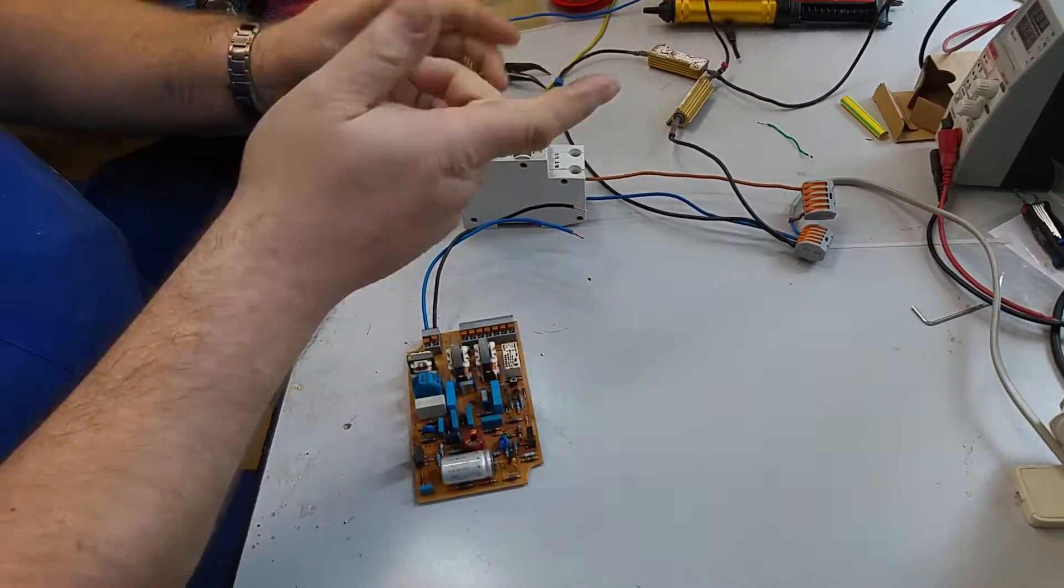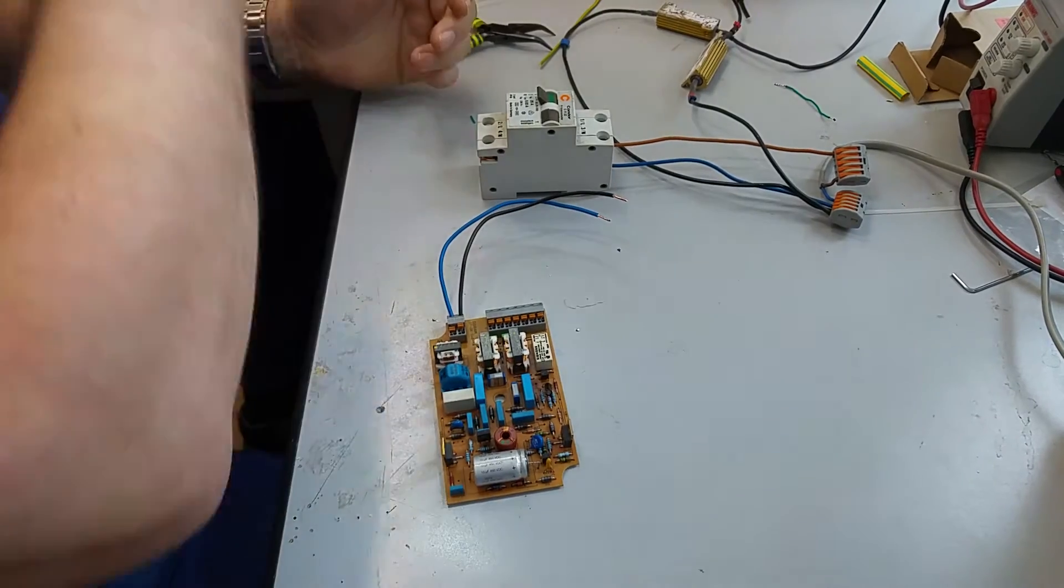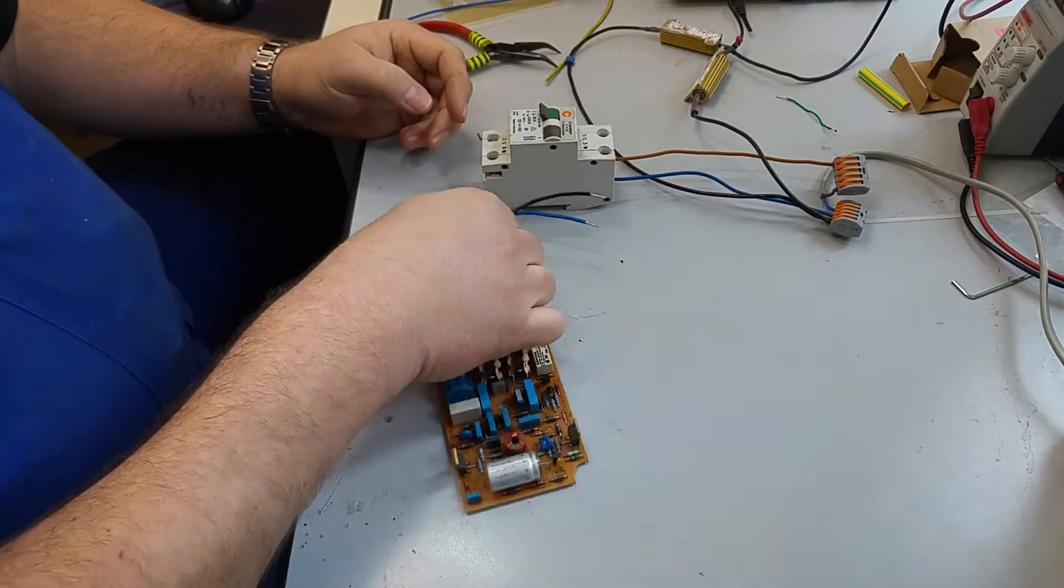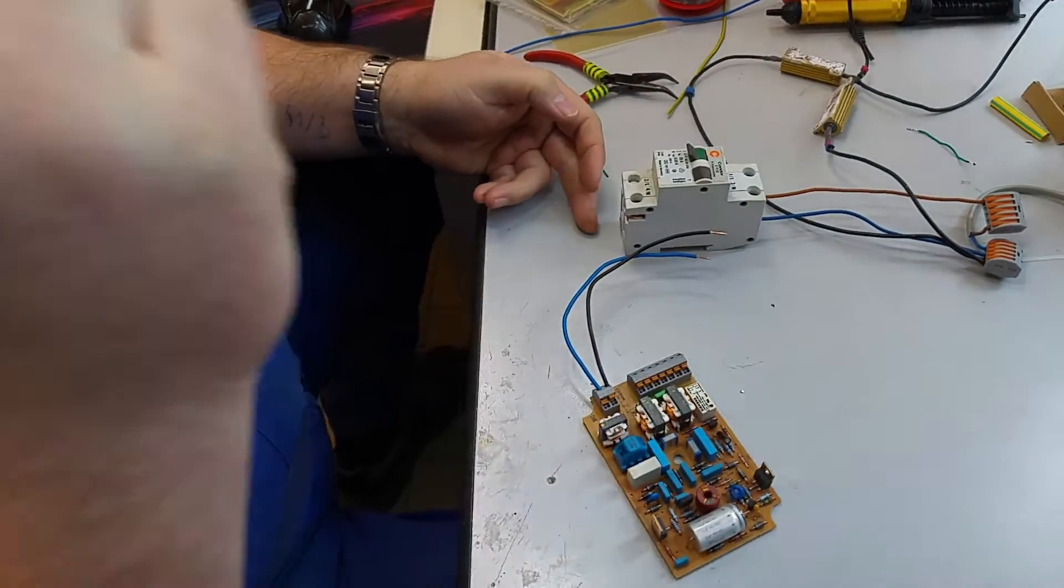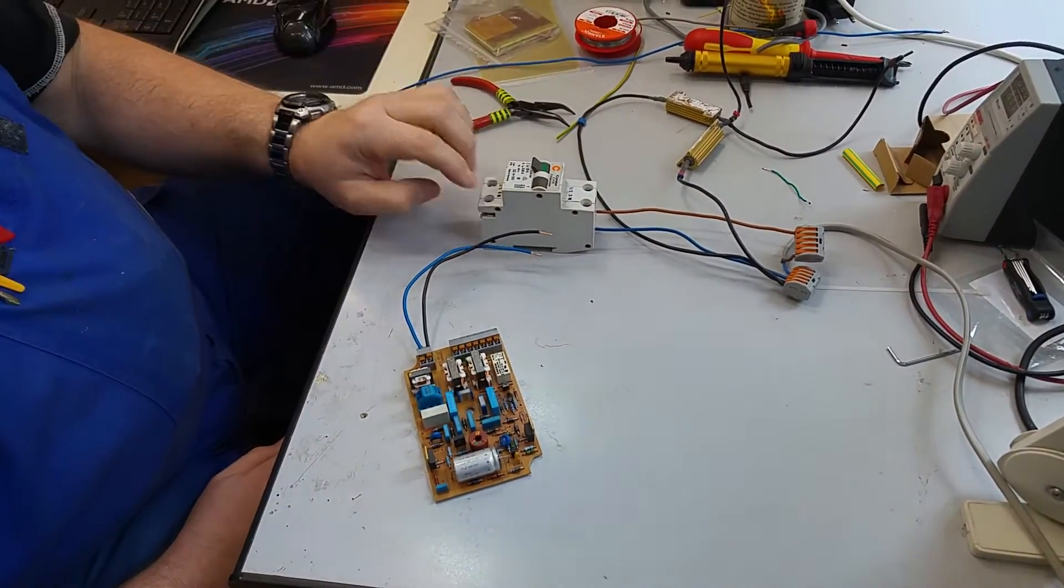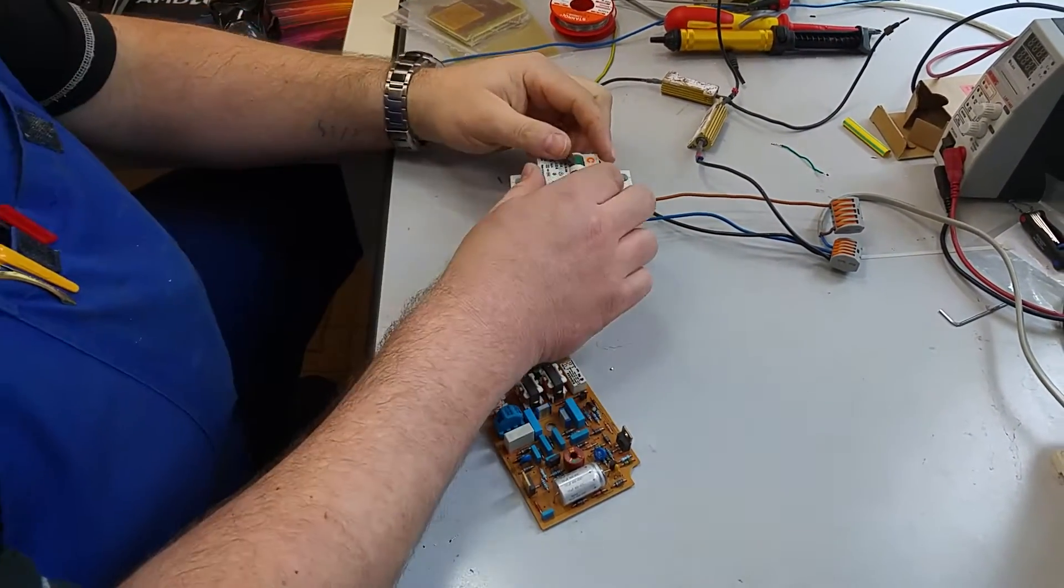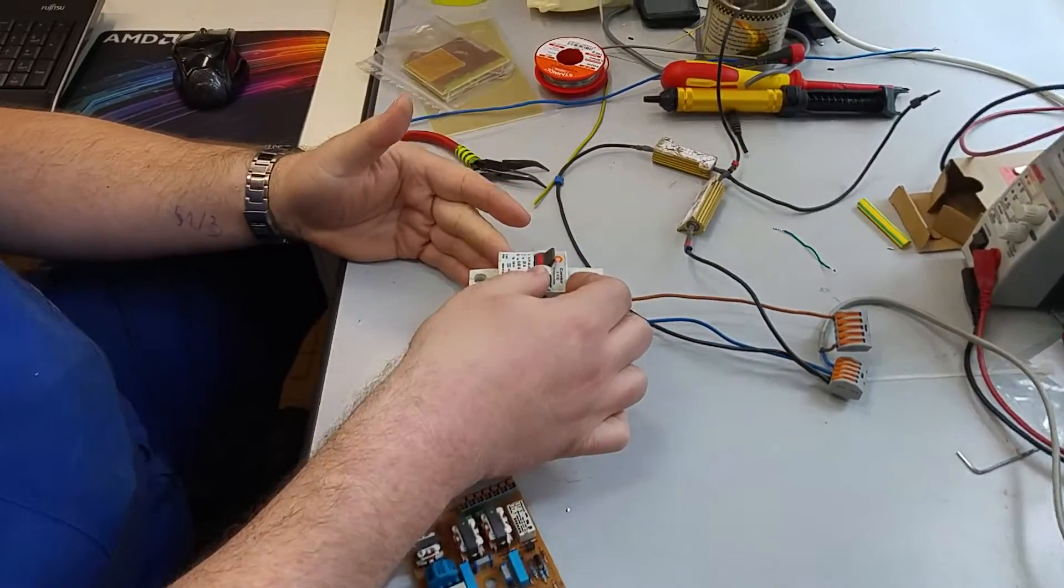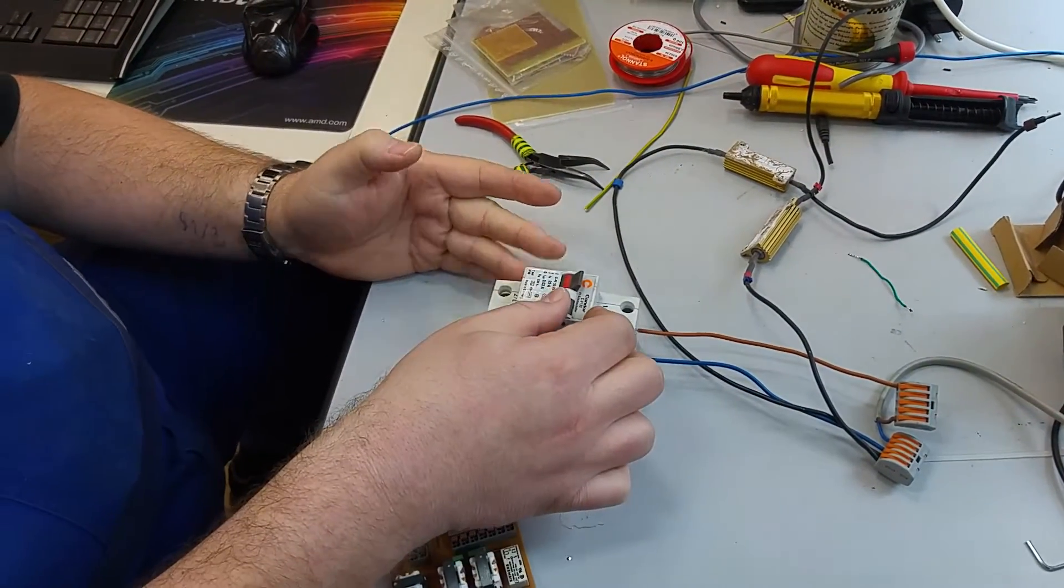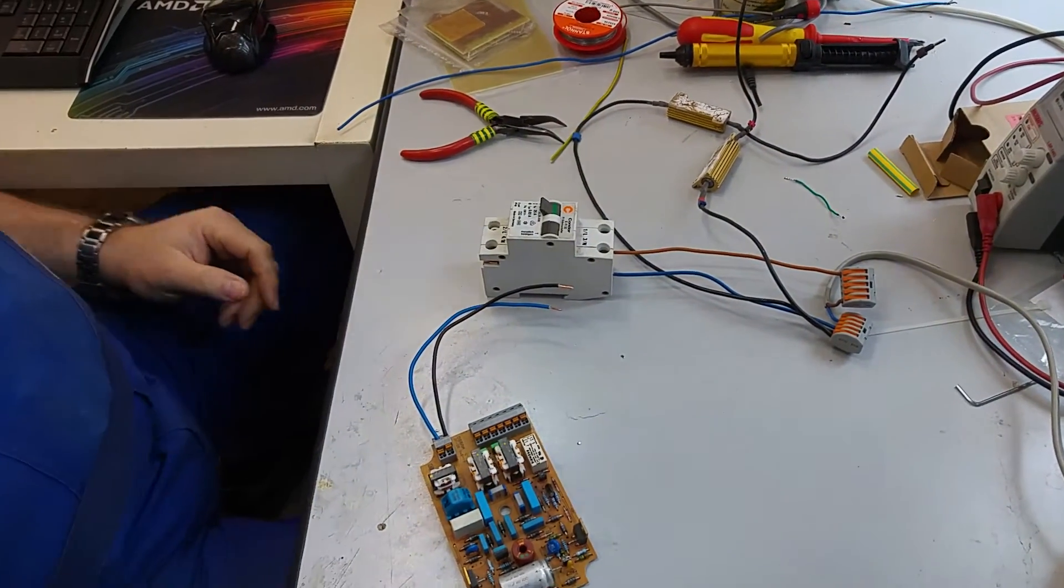Power is on. Nothing is on. Nothing is connected to the protected side of the RCD. I switch it on. Try the test key and it trips like it should. Again, it's still working, perfectly normal.